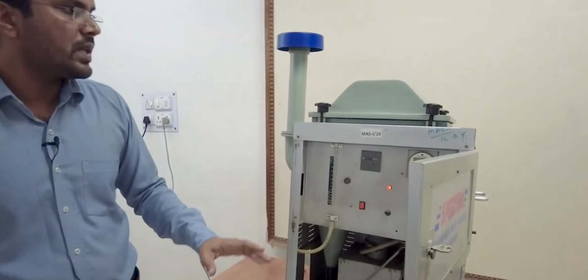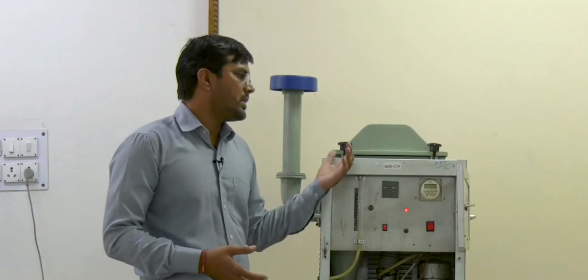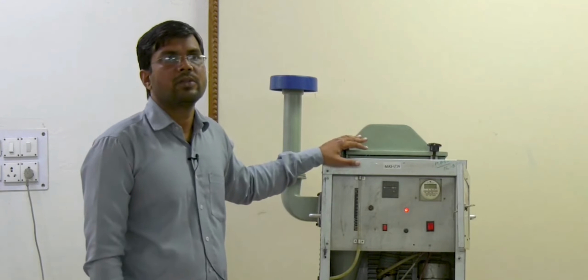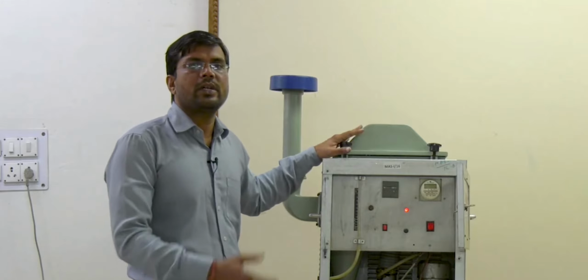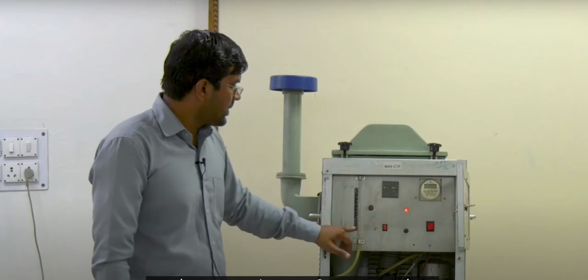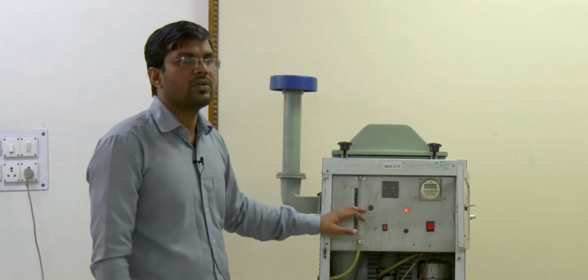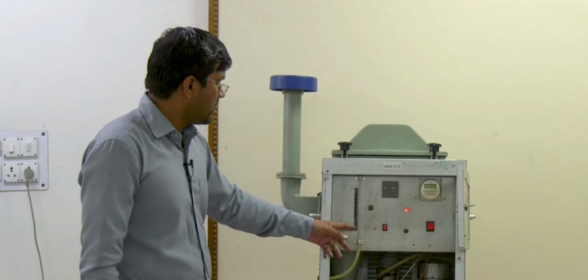Now the question is, when we place the device in ambient air and do the sampling, initially our filter will be clean, so there will be little resistance for the air to pass through it. As we go further, the filter starts getting dirty, the pressure drop will be relatively high, and because of that the flow rate will go relatively down. Now the question is which flow rate we should take. The point is to take the representative flow rate.